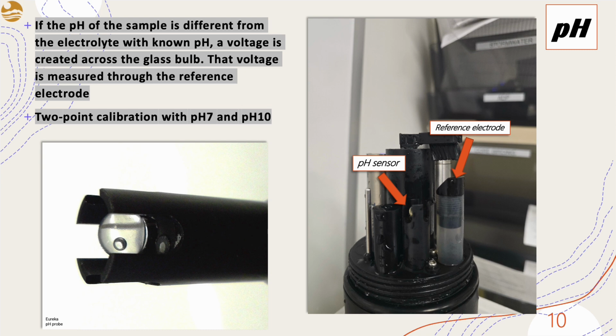Since the pH value at Tempe Town Lake is relatively stable, our pH probe will be calibrated with only a 2-point calibration with known buffers of pH 7 and pH 10. In other studies where the pH can be significantly more variable or requires high accuracy, a 4-point or even 10-point calibration can be performed.